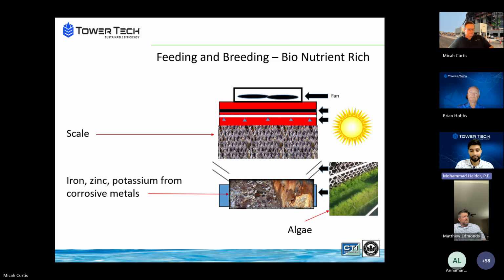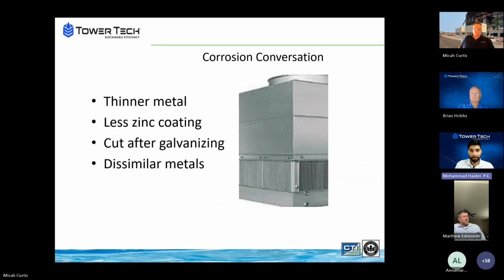So, the first picture at the top, what you see is scale, which is just mineral deposits when dissolved solids precipitate out of the water. So that's actual mineral deposits, such as calcium, that precipitate out of the water. Below that, you see actual corrosion, which is metal degradation due to chemical reactions. So dissimilar metals, which we're going to get into a little bit later on, means using two different metals, and you're essentially creating a galvanic cell between those two metals, which accelerates corrosion much more than if you have, for example, a uniform metal.